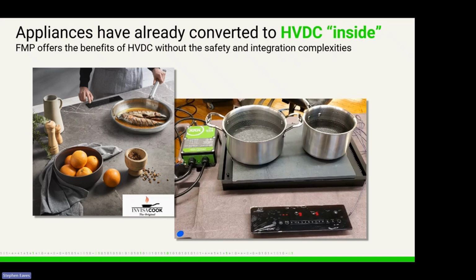On the right is the module underneath that countertop, which is the induction cooktop module, and it's operating on DC. We're not converting back to AC. The receiver sends 336 volts DC into the induction unit, and it works just fine, actually better than if it had to rectify AC. This is a very efficient installation, with a very thin wire coming up from the basement to the stove, and a very efficient conversion. The green box receiver is about 99.6% conversion efficiency while powering that induction unit.